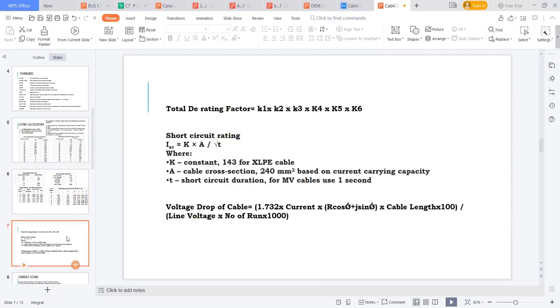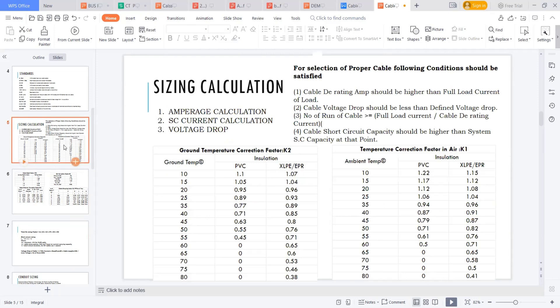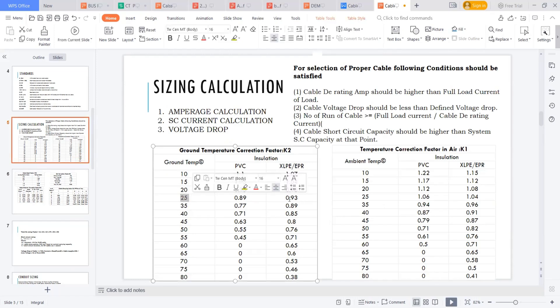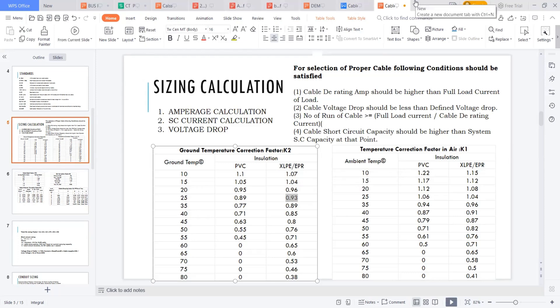Suppose I am laying a cable inside the ground. I selected an XLPE cable and I am laying it at a ground temperature of 25 degrees. The derating factor I have to multiply is 0.93. So if I am selecting a 400 square mm cable which is carrying 1000 amps, so 1000 into 0.93 gives me 930 amps only.